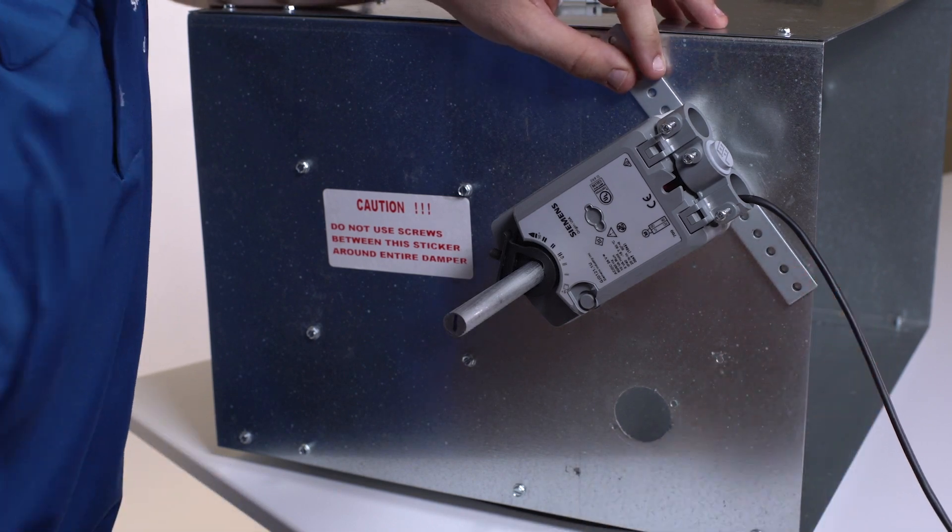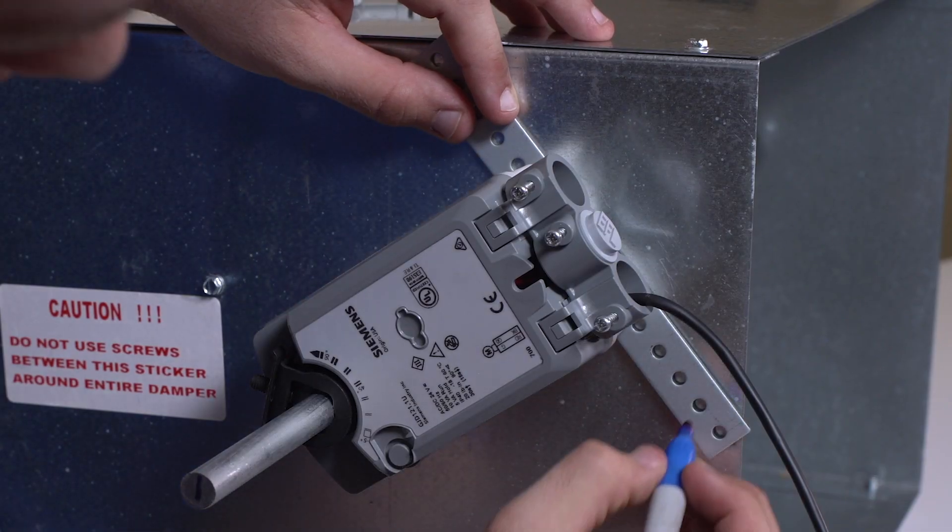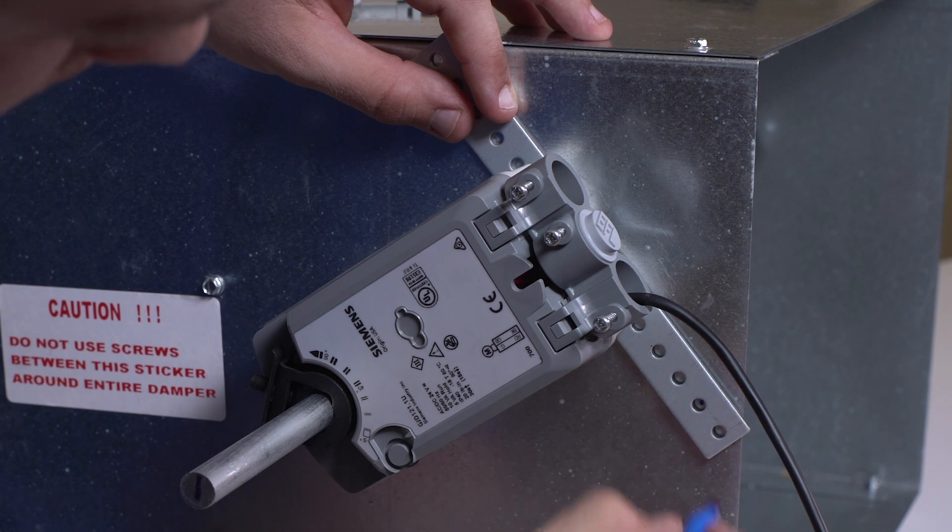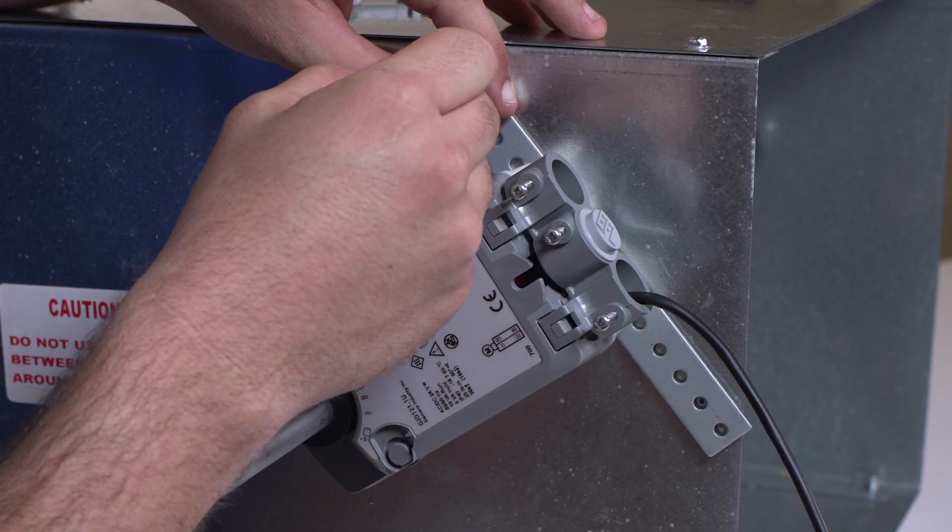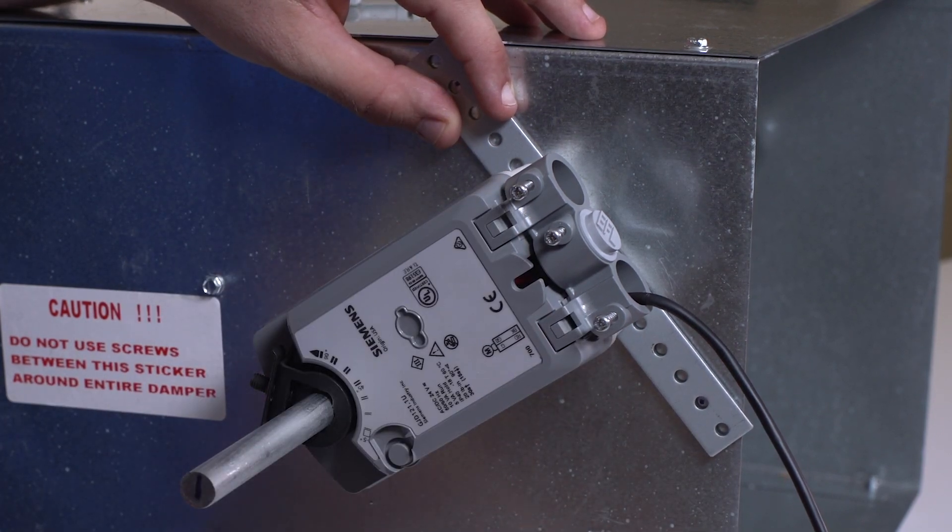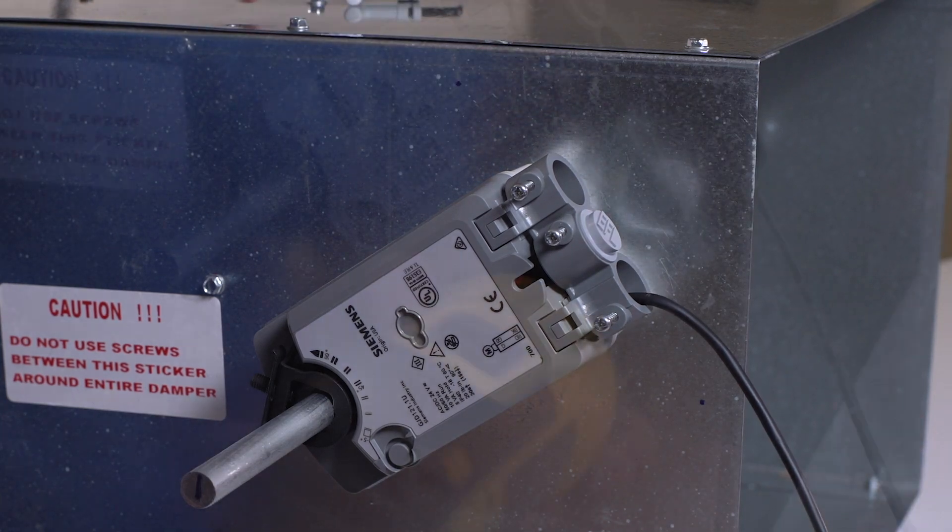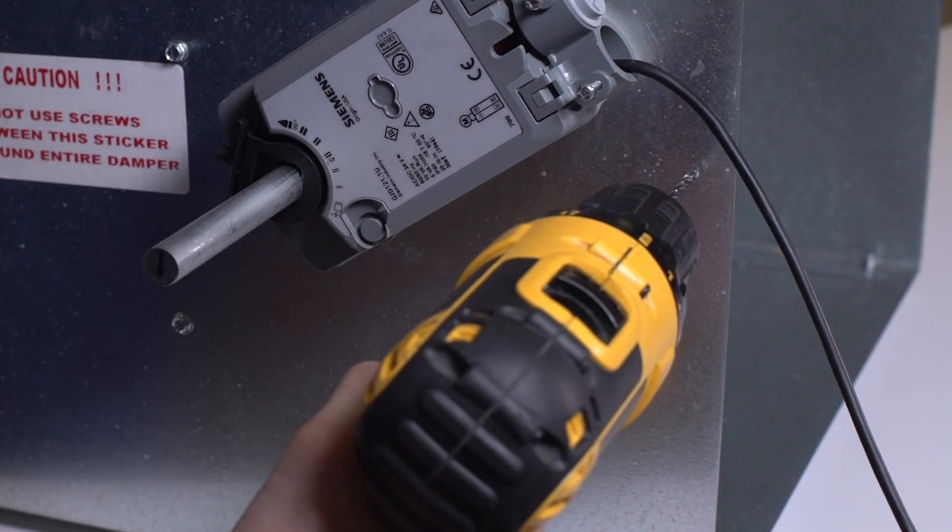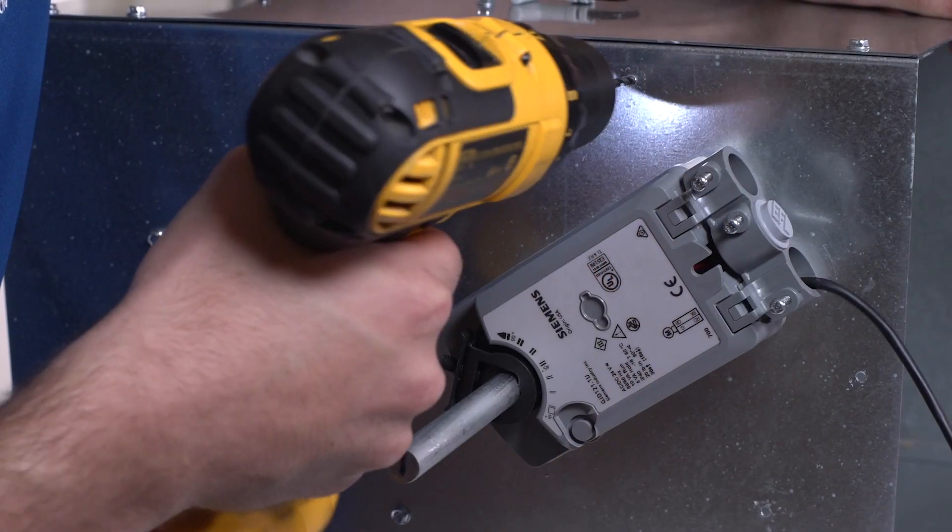Next, insert the anti-rotation bracket and orient to the damper as necessary. Keep the bracket to the center of the slot at the bottom of the actuator. Drill a hole at each end of the bracket and secure with self-tapping screws.